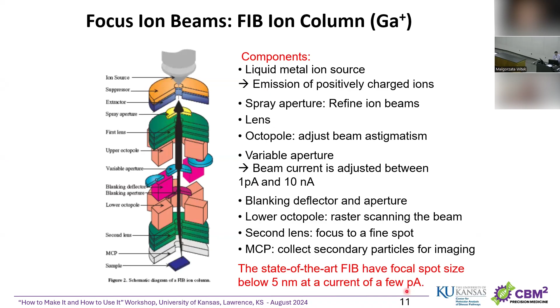And then you have a second lens to get the final focus, and then you have the sample here. So if you have this state of the art FIB, normally you can reach a focal size as small as 5 nanometers, and the beam current is as low as a few picoamps. But that is the optimized case. In real cases, it's hard to get down to such a small beam size and beam current level. So now, when these ion beams collide into the substrate, what happens?